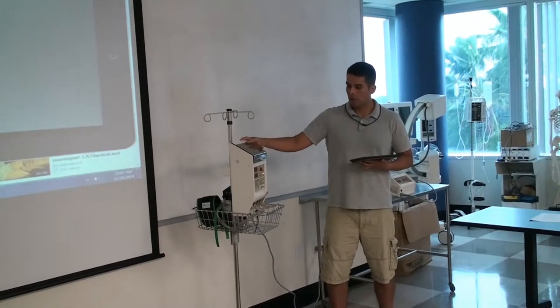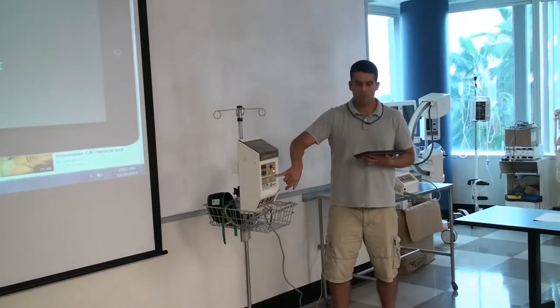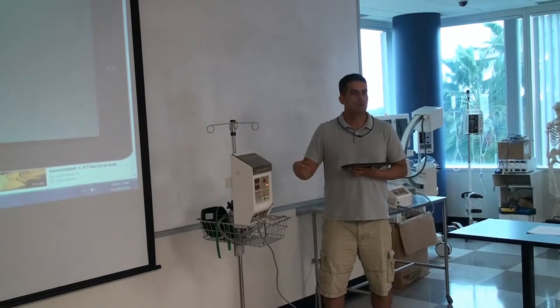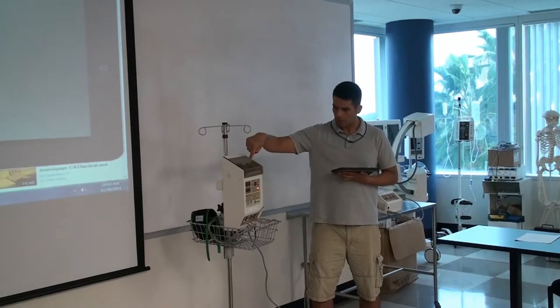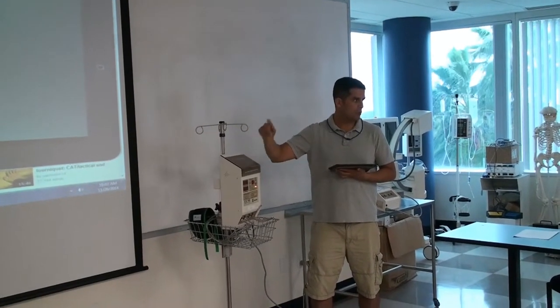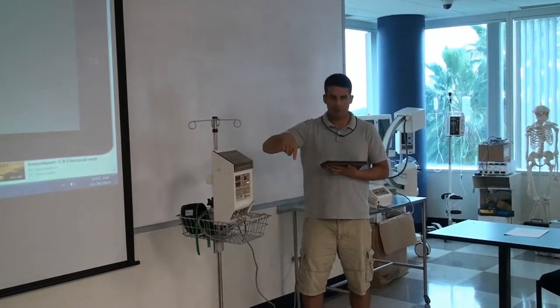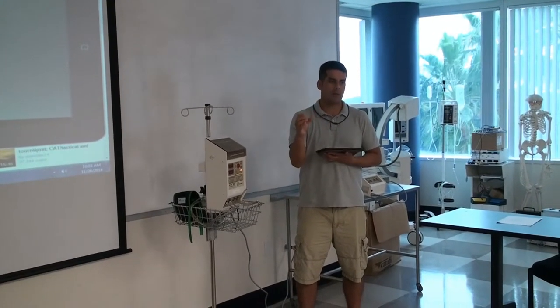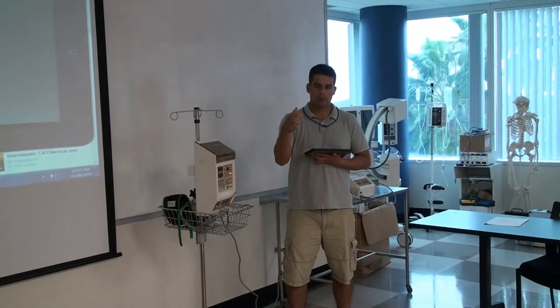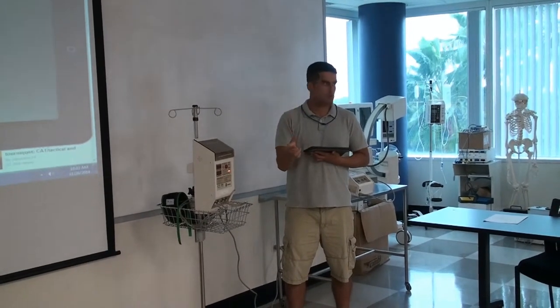After you initiate the calibration mode, you press inflate for the main cuff. So the unit will start adding pressure. The pressure has to be equal to the pressure that you have in your calibration measuring device.